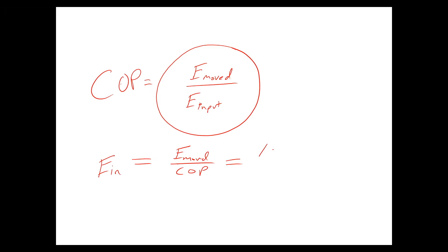So if you saved a hundred thousand kilowatt hours in some energy project, the air conditioning savings for the electricity for the air conditioning, you would have to go by this equation. And if the COP was three, your electricity savings from air conditioning reduction would only be about a third.